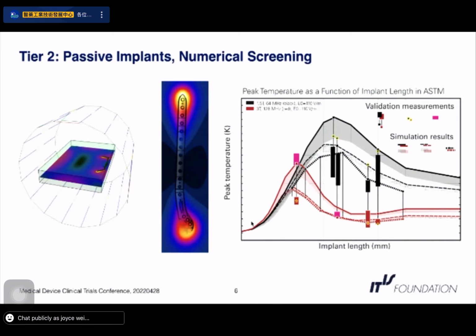And here you see a graph showing, in red for 3T and in black for 1.5T, how the peak temperature rise that can be caused by an implant depends on the implant length. And you see that it's a curve that gets to a maximum and then goes down again. But this is only valid for short implants. If we get longer, elongated implants, like spinal cord stimulators, for example, we have phase effects that we have to consider, and that's why we would move to tier 3 assessment of these implants, which can cause much higher heating than what you see here.